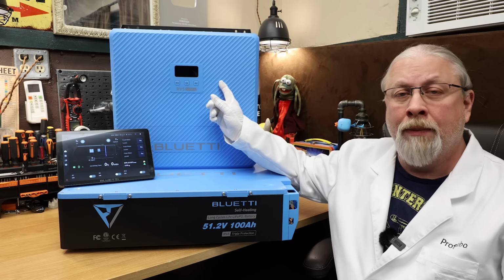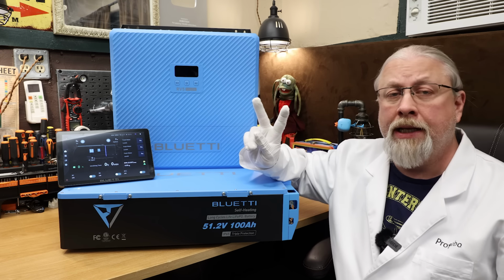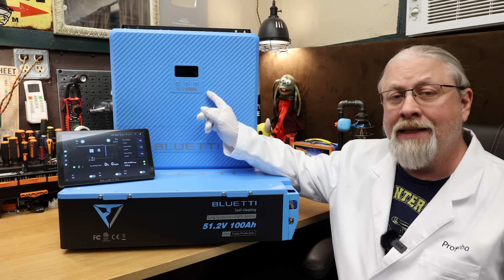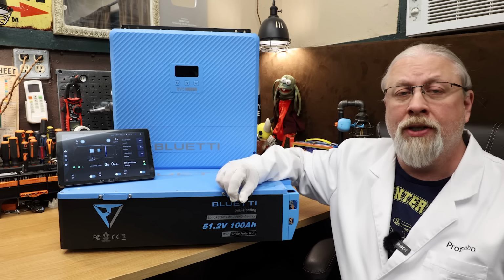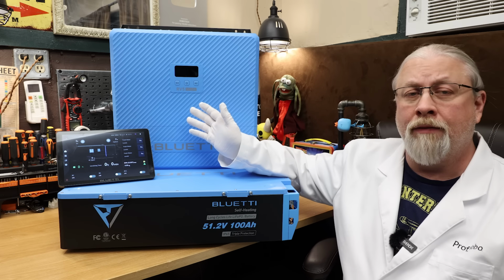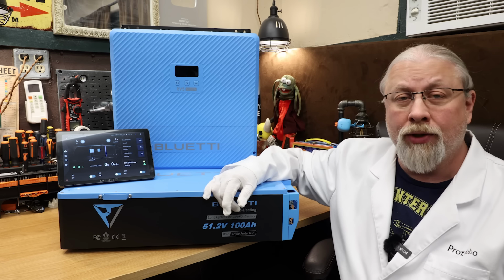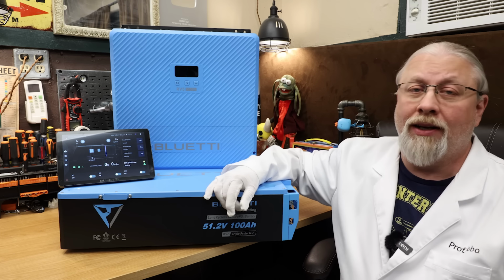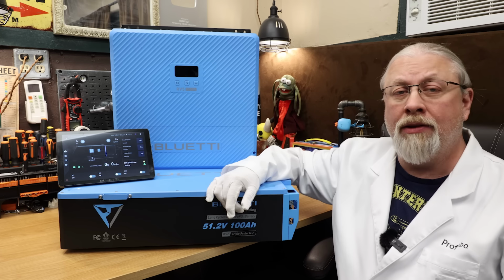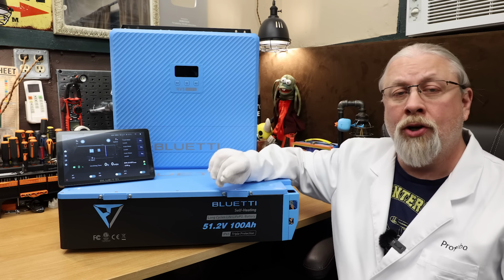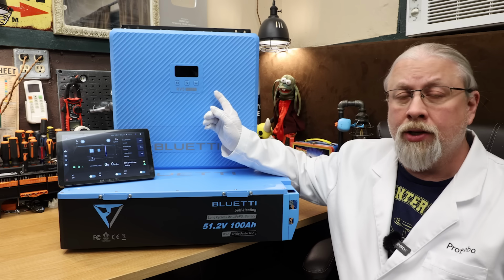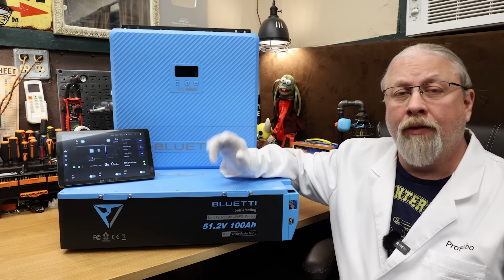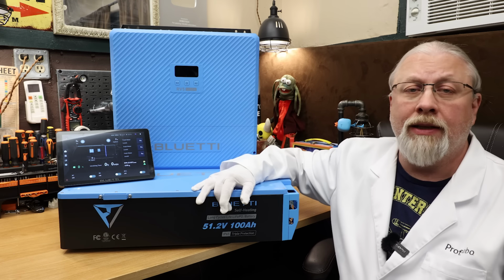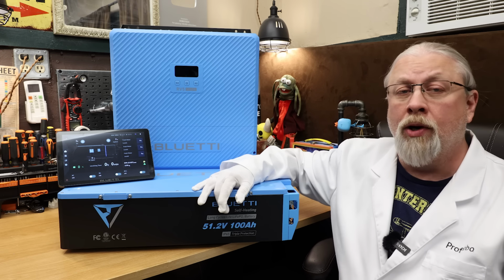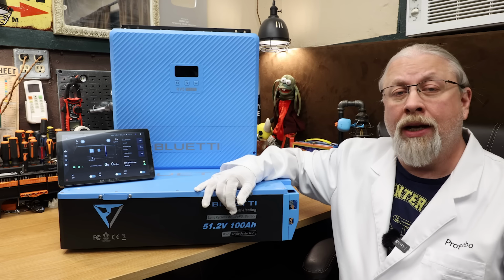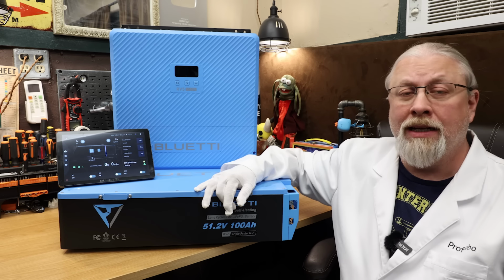The RV5 Power Hub inverter holds the brains, 2 MPPT solar controllers, the 5,000 watt AC inverter, which also doubles as the battery charger, and something unusual for an off-grid inverter, a dedicated 100 amp 12 volt regulated DC output. Also unusual since this is designed to be used either as an off-grid home inverter or an inverter charger in a vehicle. One of the 2 MPPT controllers can be switched into a different mode from solar PV to vehicle, to allow 12 or 24 volt alternator or external battery bank charging. This leaves 1 MPPT free for solar use up to 1800 watts of panels.